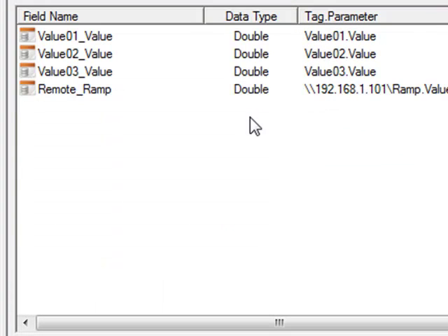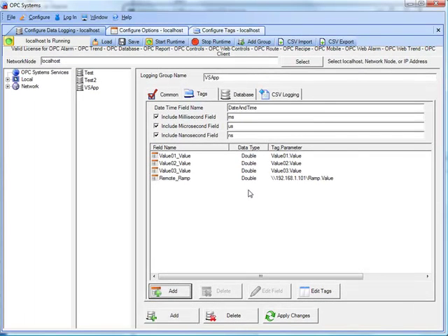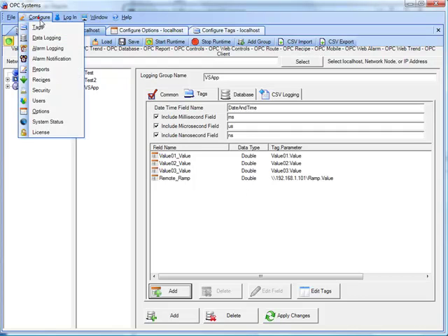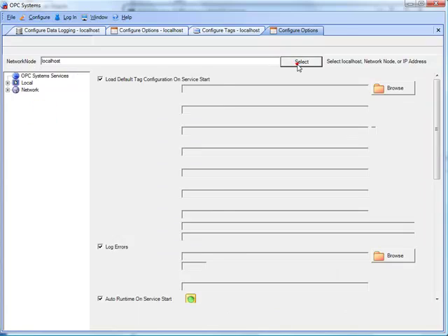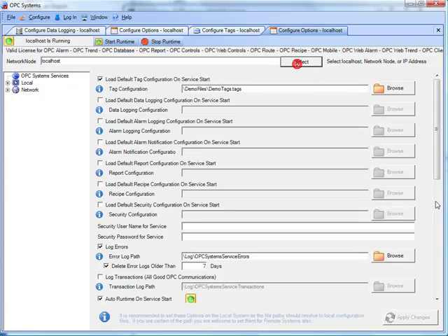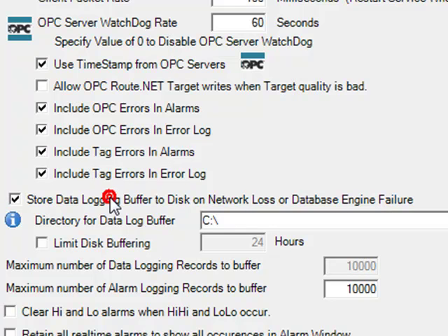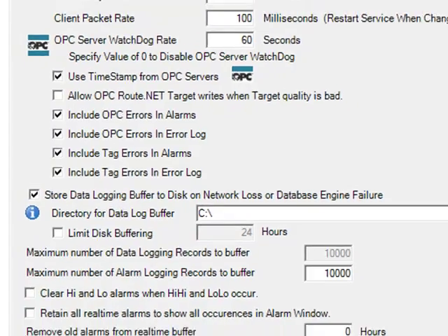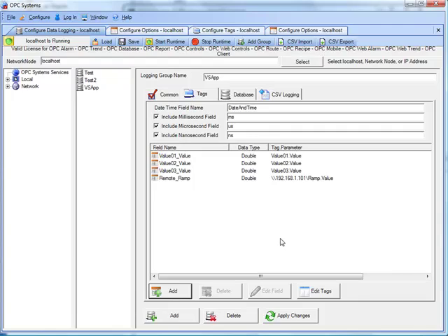Once a connection is established, and the network connection between the data logging service and the remote service is temporarily lost, we will buffer data on the remote service, and remember to take advantage of the data logging buffering to disk found under configure options, so that the amount of data to buffer during that network loss is only limited by your hard disk size. That is found here under the feature store data logging buffering to disk. And again, because we provide queuing in all opcsystems.net features, you can still maintain 100 nanosecond resolution from that remote data source, even if you're logging across the internet.